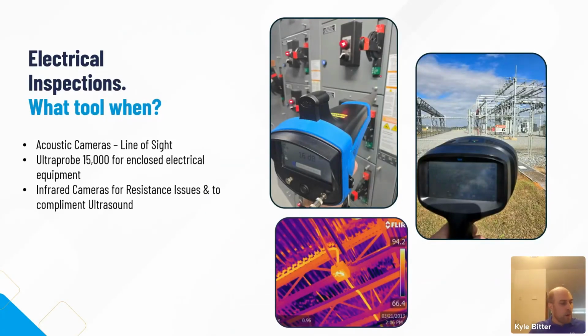So we talked a little bit about having the proper tool for the proper application. I mentioned earlier that acoustic imaging cameras are very directional and need straight line of sight. Ultrasound does not penetrate through solid objects. As you can see in the picture, upper left-hand corner, they're using our Ultra Probe 15,000 to scan the seams of that electrical asset, maybe a vent if available, to listen inside to hear what's going on. Often I see little IR windows now being developed with ultrasound in mind, where you can stick your Ultra Probe into those electrical assets to hear what's going on. If everything is safe, I can then safely open up that cabinet, use my camera, and do further diagnostics at that point.